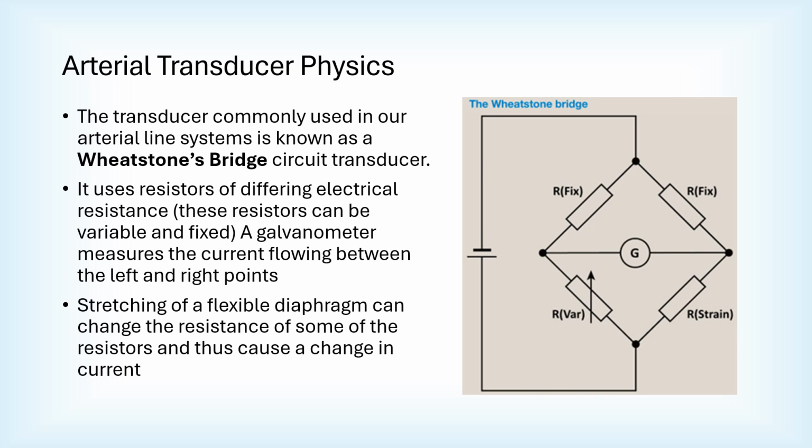The measured difference in current caused by the difference in resistance is used by algorithms to calculate the pressure waveform required for such changes. Additionally, modern-day strain gauges may have all resistors with variable resistances and more complex algorithms to convert current into the pressure waveform.